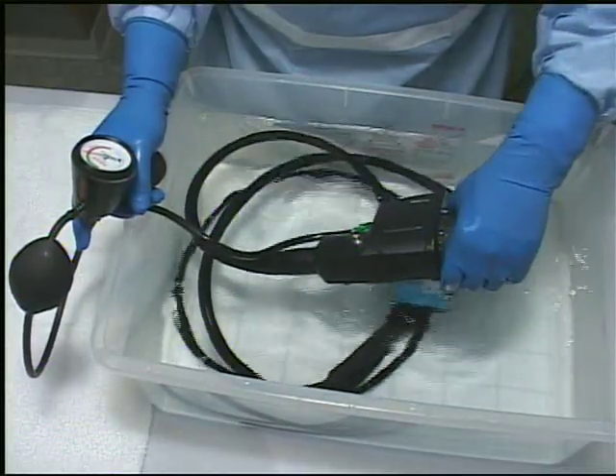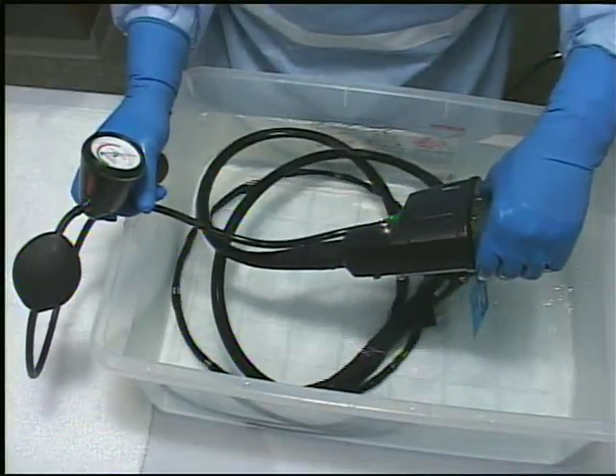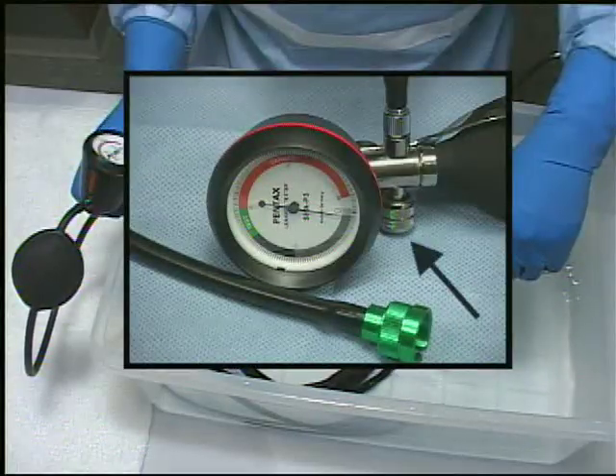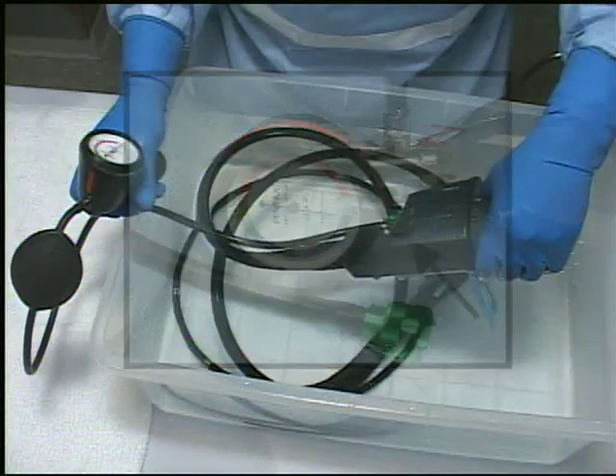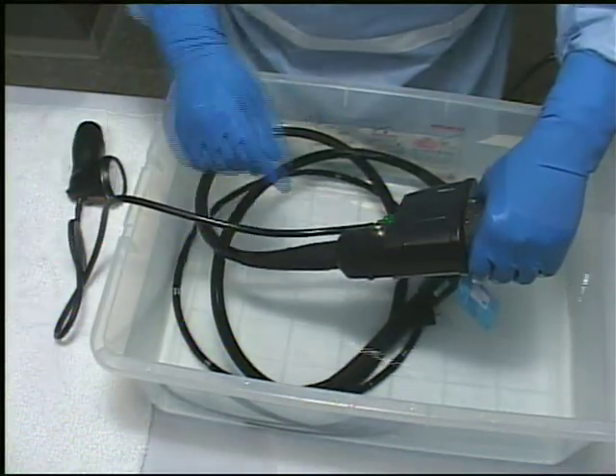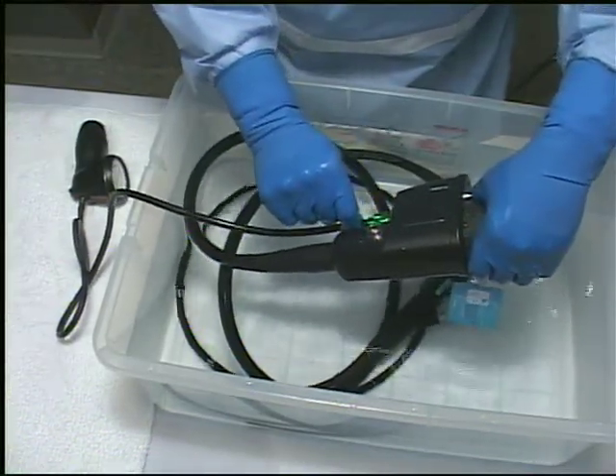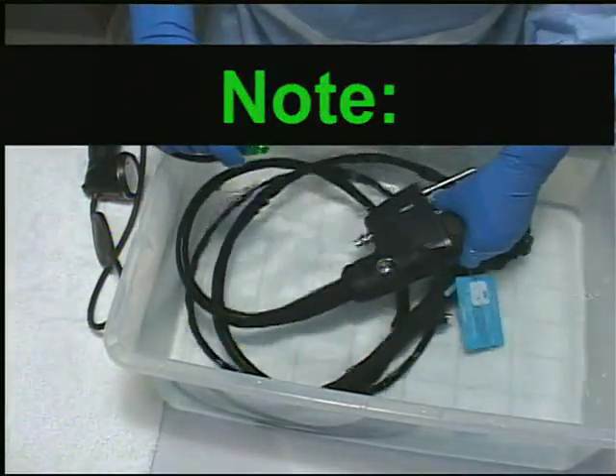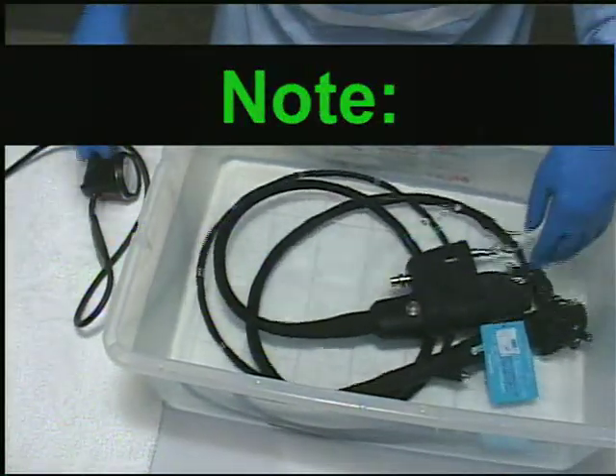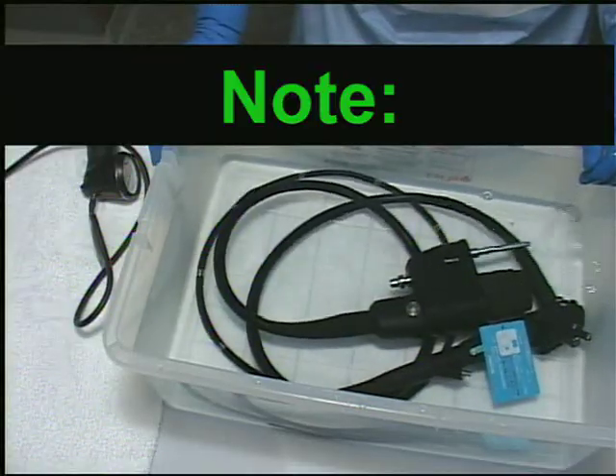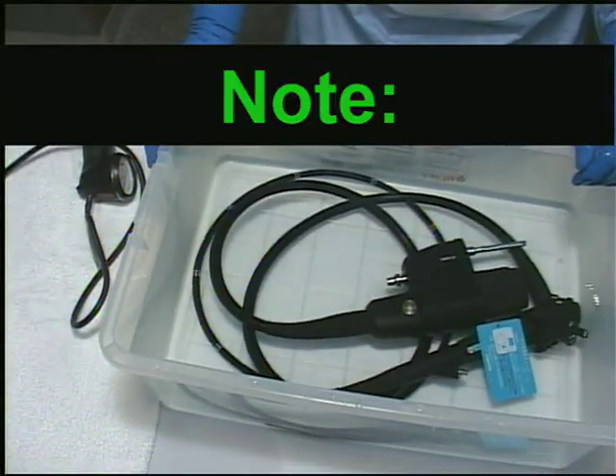After removing the scope from the water, release the air pressure within the scope by opening the pressure release valve on the handle of the leakage tester. After the gauge indicates 0, disconnect the leakage tester from the scope. Note: never connect or disconnect the leakage tester underwater. This will cause leakage of water into the scope and leakage tester.